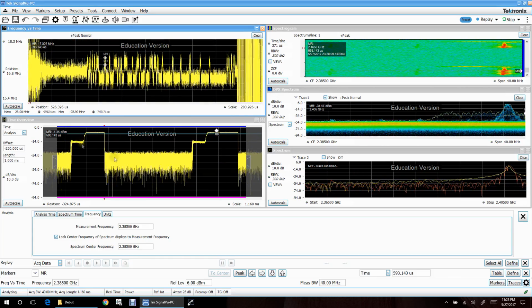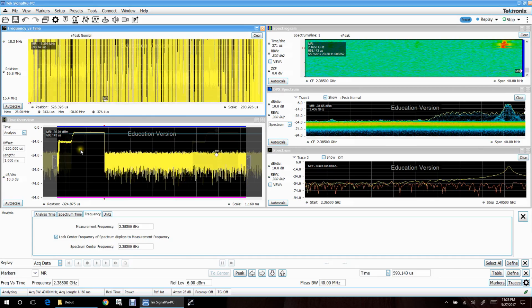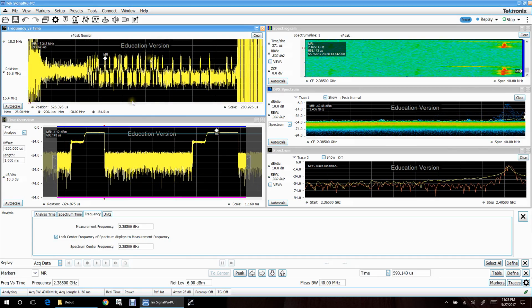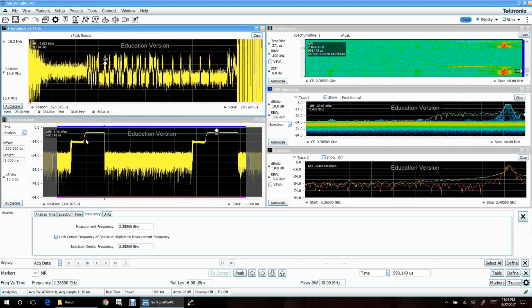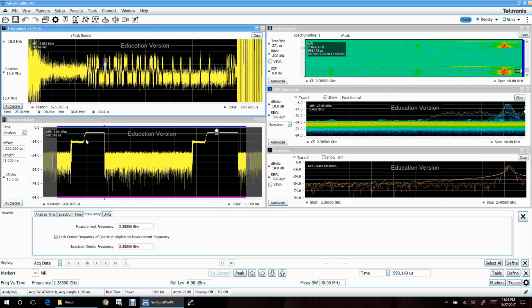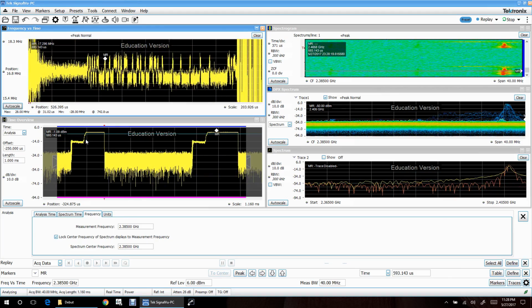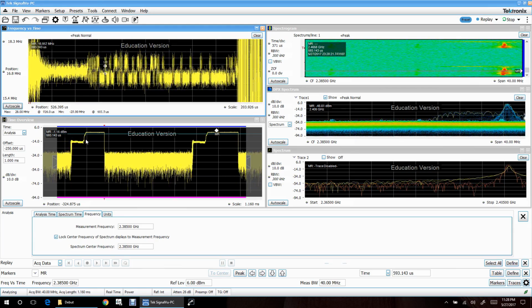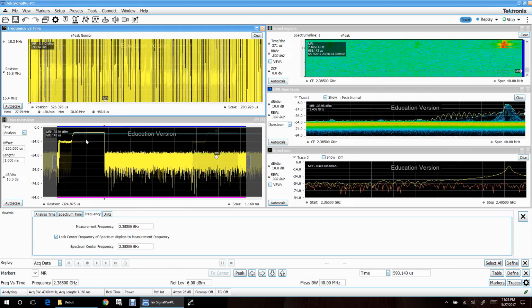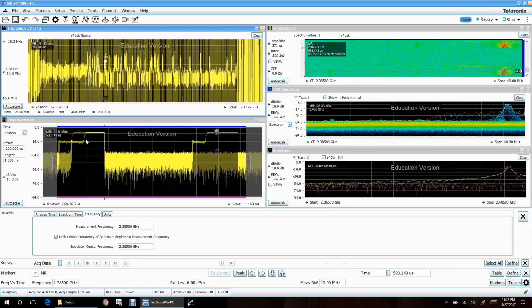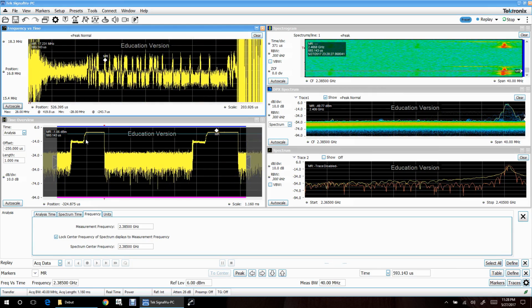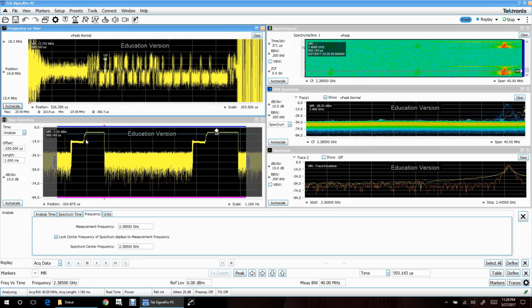We still have the issue that the trigger sometimes triggers on the long pulse as opposed to the short pulse, and that's why it's jumping around still. And that needs a dwell time or a hold off time in the trigger menu to resolve that. And I really hope that these two changes would be implemented, because they would be an enormous advantage. As you can see, the limitations of not having these two trigger functionalities make the measurement quite a bit more difficult.